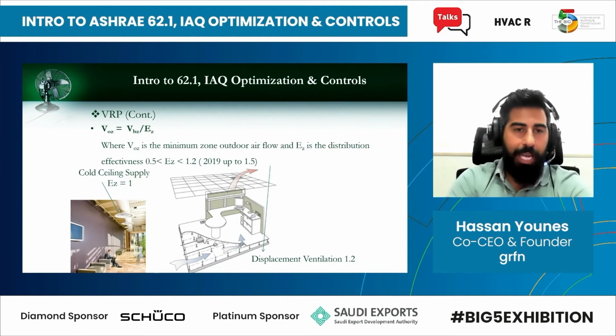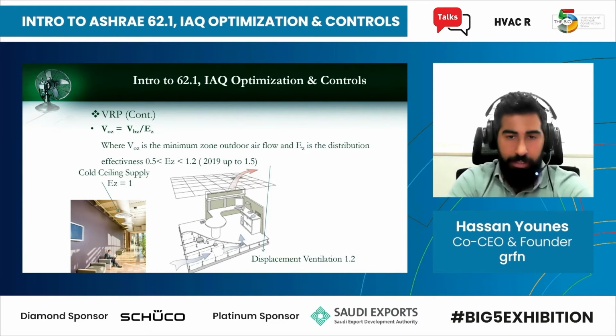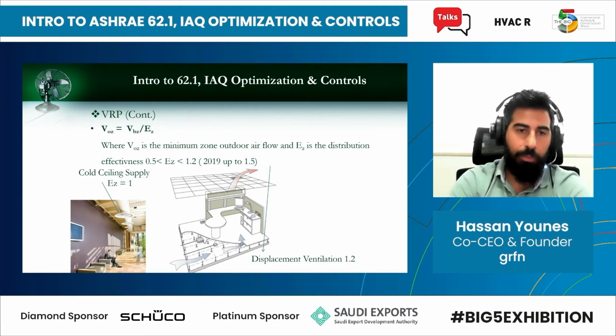Now, once you get to that number, you need to divide by the distribution effectiveness. And that depends on the type of distribution system you have. In general, in buildings in the GCC, you'd find cold air supply from the ceiling. So that will give you an effectiveness of 1. So the number that you calculated in the previous step will remain the same.